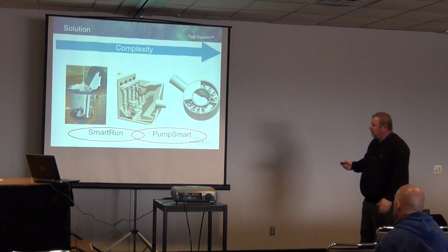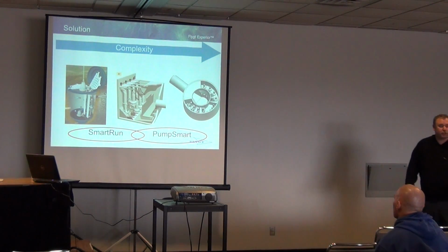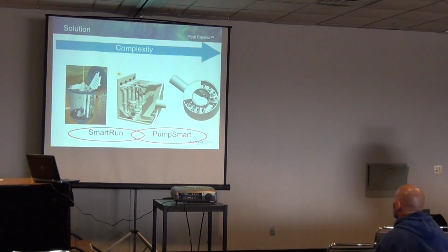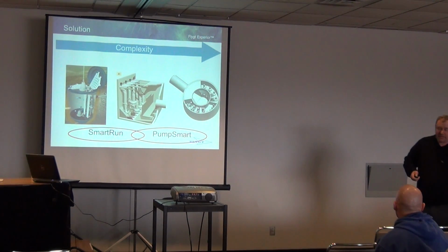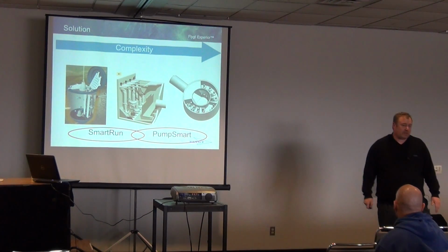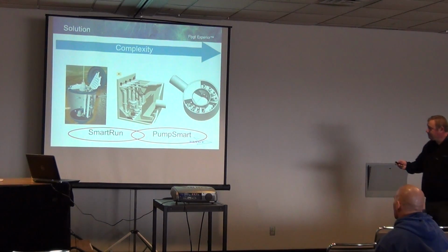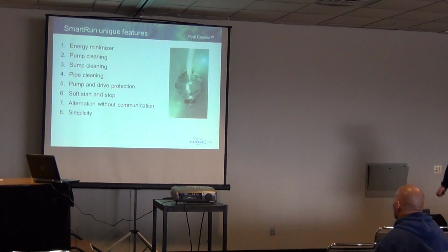So what is it designed for? The Smart Run controller is designed for duplex stations only. If we get into triplex, quadplex, bigger stations, then we have to go to more advanced type controls. But this is designed for the typical duplex station from that 3 to 105 horsepower. So what kind of functions does this have? It's got an energy minimizer on it, and we're going to get into that a little bit deeper.